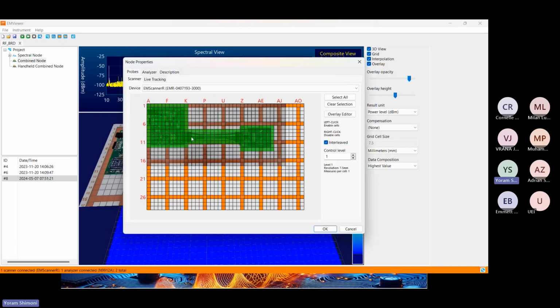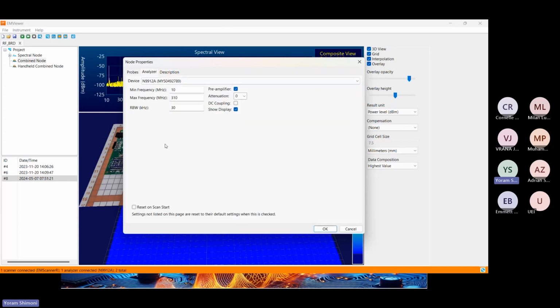So this is the way I select or set the scanning. It's going to be just a regular resolution scanning. So essentially I selected that entire area. Just did it before, but that's the way to do it. You select the cable and then the RFID transmission area. Here you're going to select the spectrum analyzer settings, in this case from 10 megahertz all the way to 310, 30 kilohertz RBW. Essentially, that will do the trick.